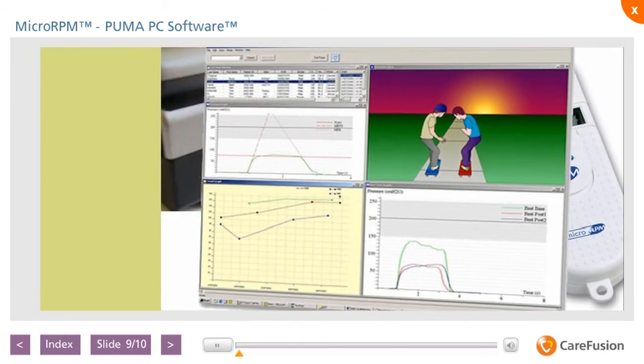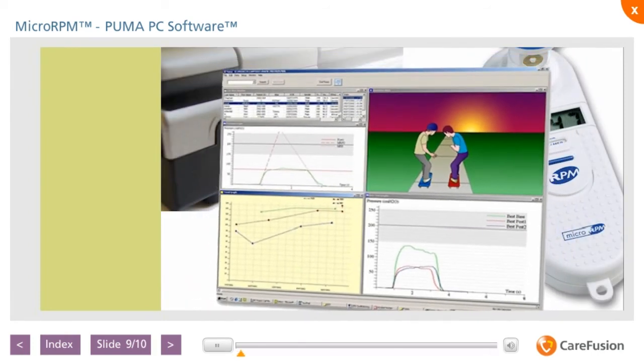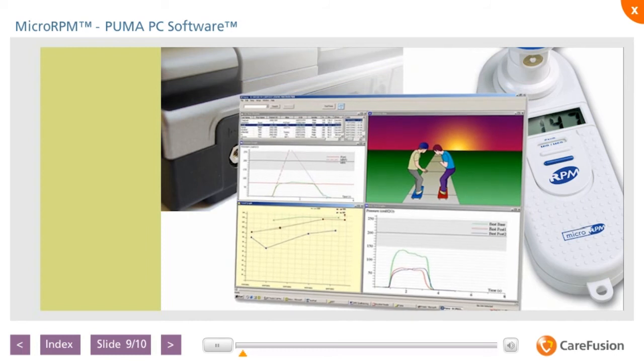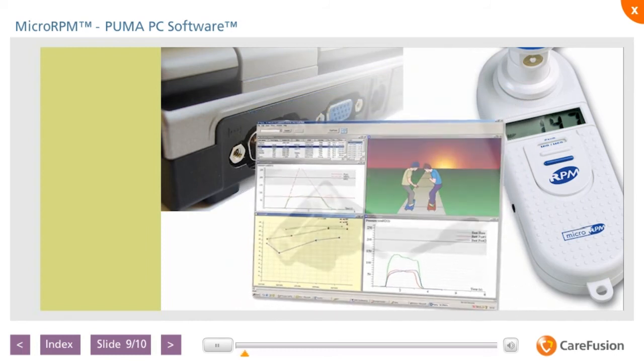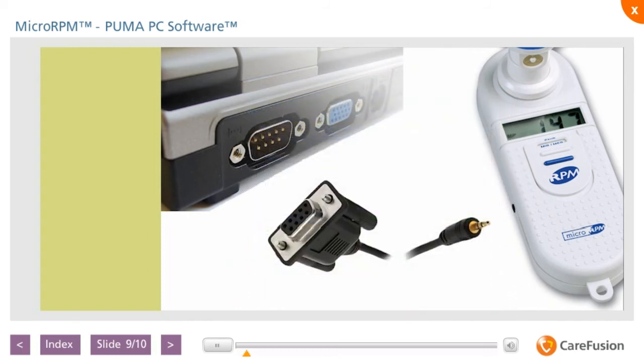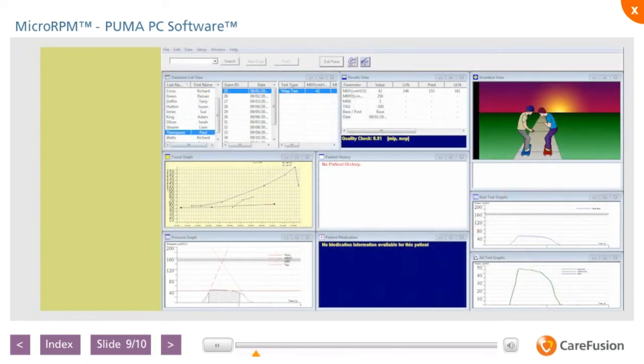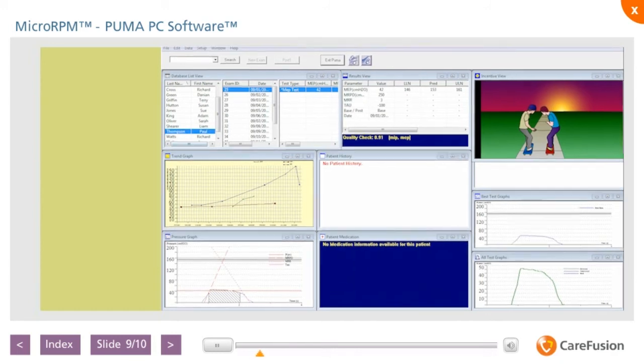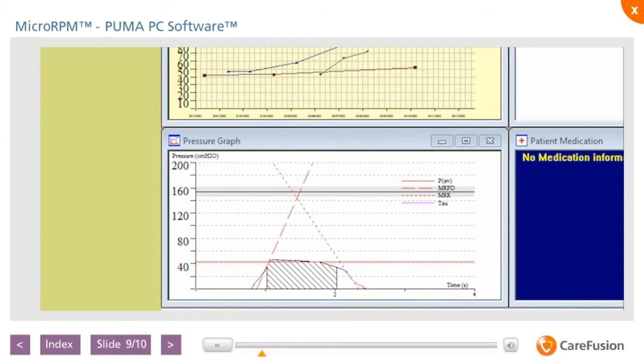Respiratory pressure measurement tests can be performed using the MicroRPM when connected to the Puma software. Push the plug into the socket on the side of the MicroRPM and insert the RS-232 connector into a free serial port on the PC. Puma is an optional 32-bit software package, compatible with all the latest Windows operating systems, for displaying the pressure waveforms developed during testing with a MicroRPM.